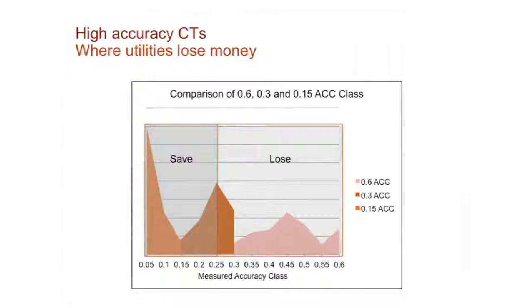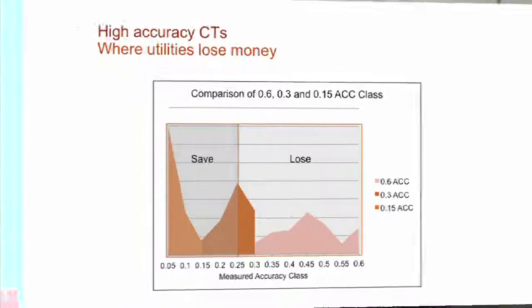Okay, so what this does for the utility is it helps become much more accurate. You'll get more revenue based on no losses in here, and the customer will get a true billing payment as well every single month. Let's talk about where utilities lose their money when it comes to this accuracy range here. Anytime a current transformer is feeding data into a meter outside of this range here, utilities really start to lose money. Right? It's not as accurate as what it can be. When you have a more highly accurate CT, that's when the utility starts to actually save money. The meter will actually register more accurately for the utility.